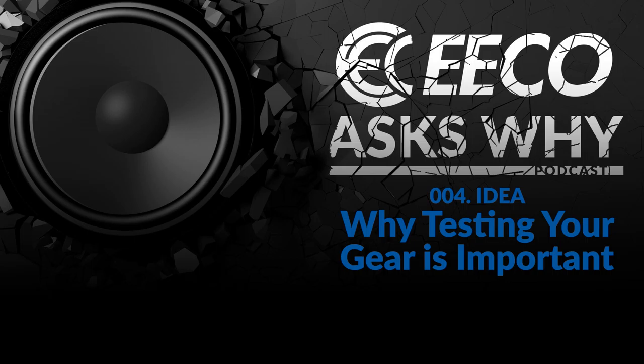And so if you're looking at a piece of switchgear that seems to be in shambles, and there's an inch of dust all over it, and doors are bent and not closing properly, you can gauge that right off the bat. You're probably going to be encountering some issues, and it's going to be more than just taking a measurement and saying whether it's good or bad. It's going to be qualified with, yeah, this breaker passed testing, but here are all the things that need to be done to get this thing to be a reliable system again. So, you know, that's kind of like at first glance.